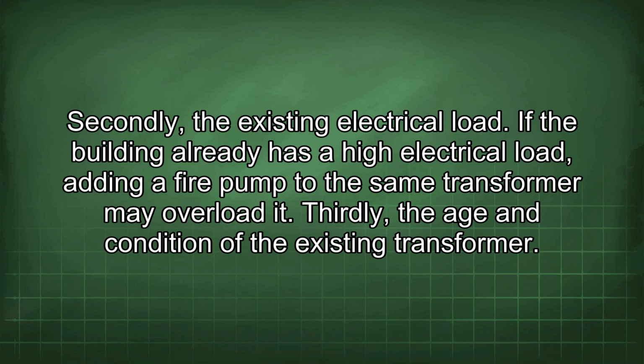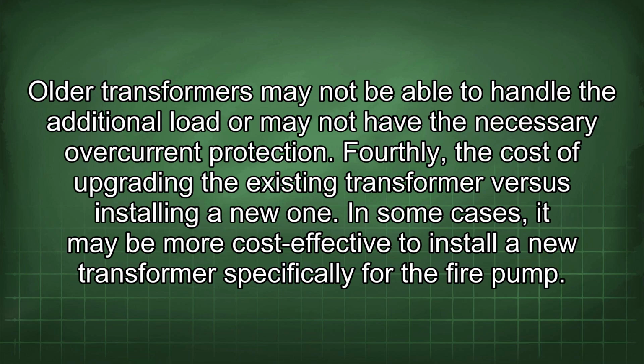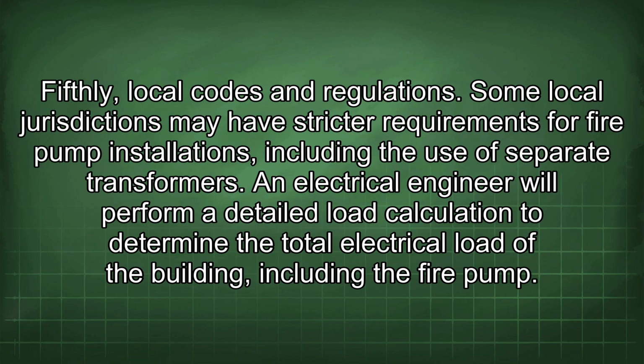Thirdly, the age and condition of the existing transformer. Older transformers may not be able to handle the additional load or may not have the necessary overcurrent protection. Fourthly, the cost of upgrading the existing transformer versus installing a new one. In some cases, it may be more cost-effective to install a new transformer specifically for the fire pump. Fifthly, local codes and regulations. Some local jurisdictions may have stricter requirements for fire pump installations, including the use of separate transformers.